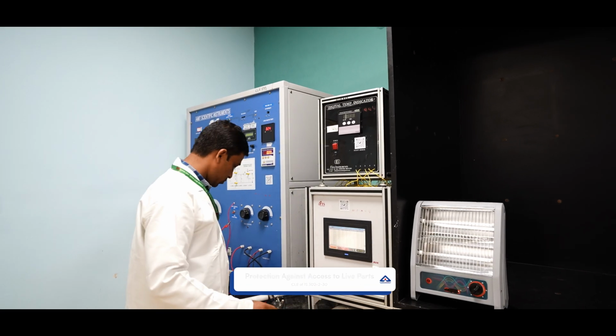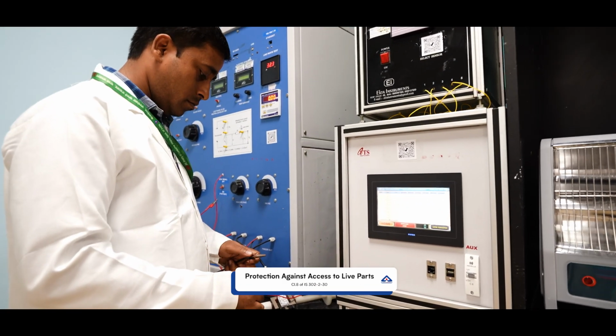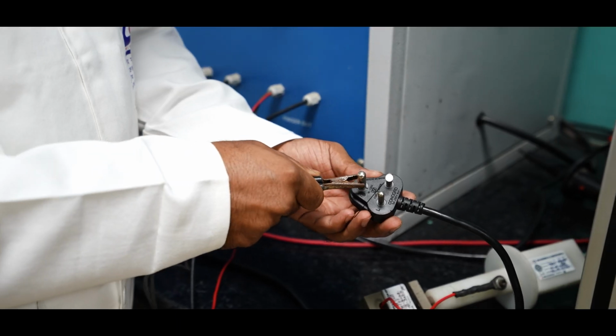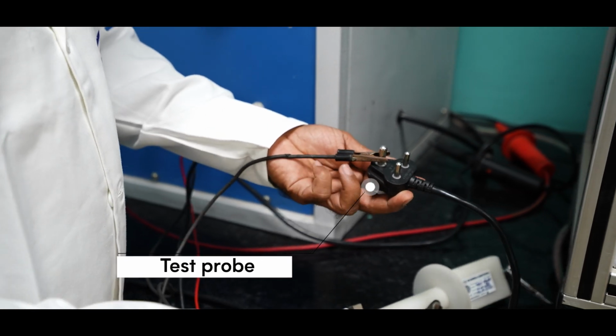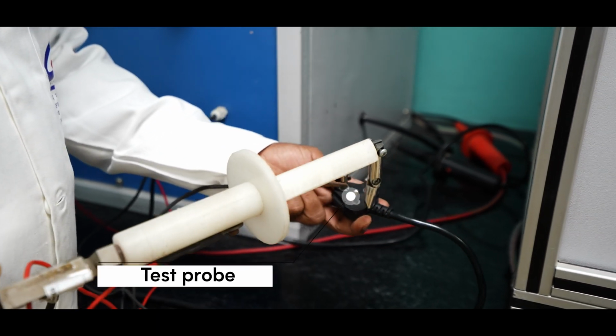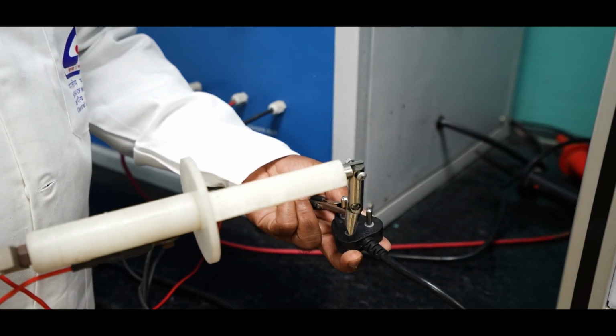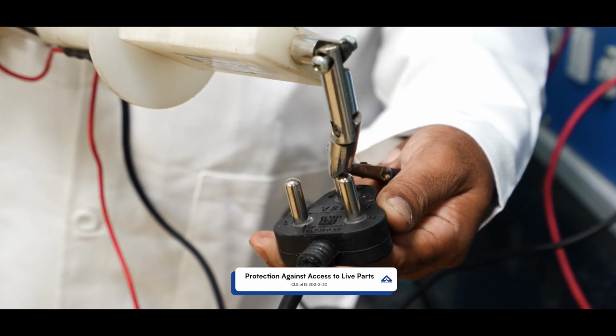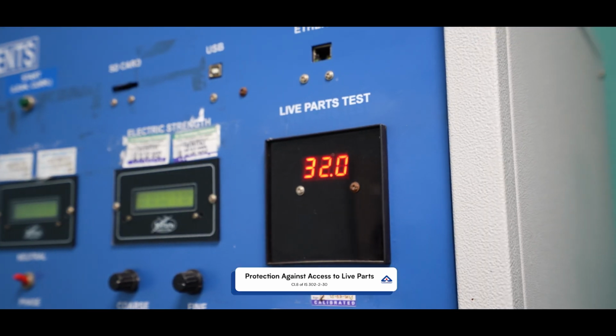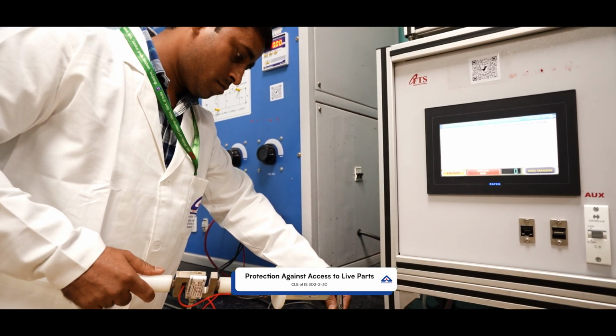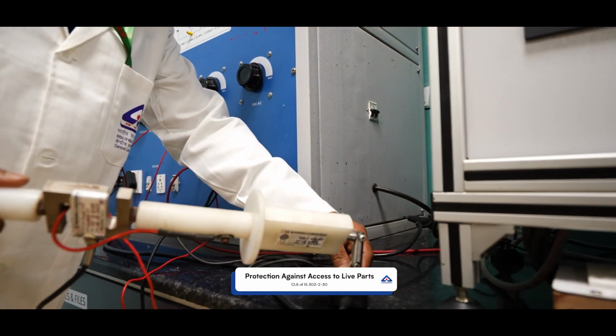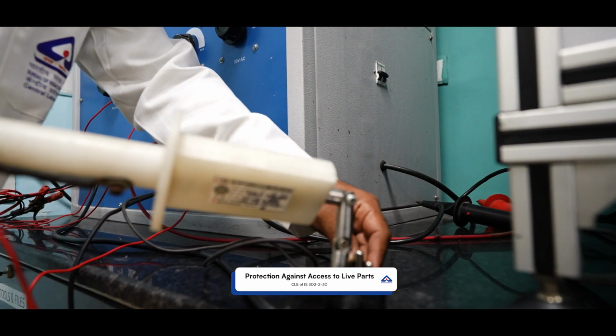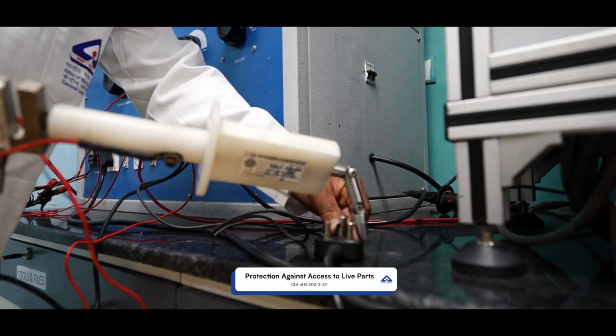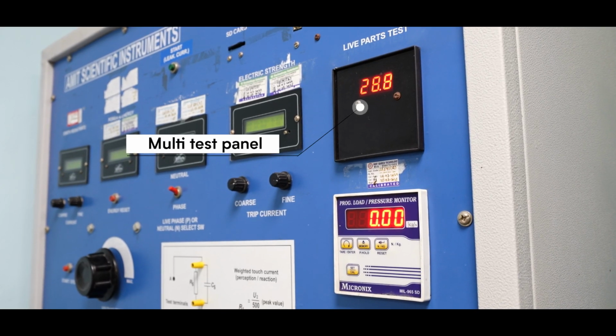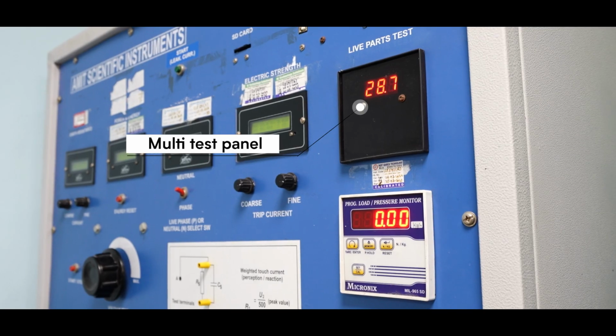One of the primary safety measures is protecting users from accidental contact with live electrical parts. To test this, we use a protection against electrical shock tester, which involves a test probe connected to the live terminal of the heater. The probe is applied to any accessible metal part of the heater, and the current is measured using a multimeter. If the leakage current exceeds 0.7 mA, this will trigger an indicator lamp on the tester, signaling that the heater fails the test. This ensures that the risk of electric shock is minimized.